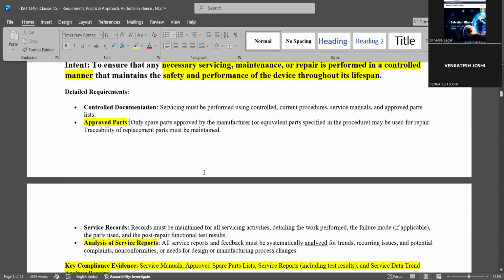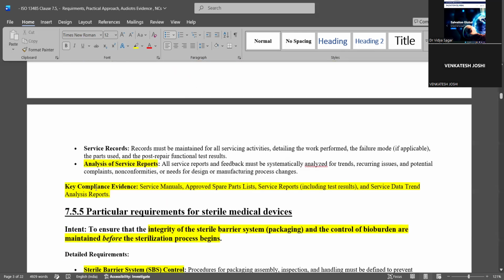You should know the traceability of that, like when I changed it. This year I changed it, and when is the next time I have to change it? You need predictability and traceability, like after 1 year, or after 100 uses, or after 10,000 uses, I have to change this spare. So you should have traceability of the parts and when to change the part, and you should maintain that in your documentation. Of course, whenever you do servicing, there will be service records.